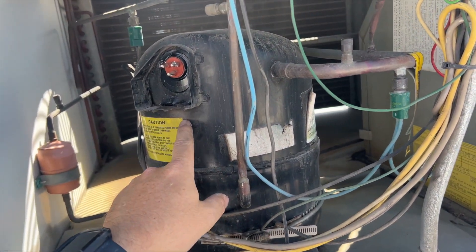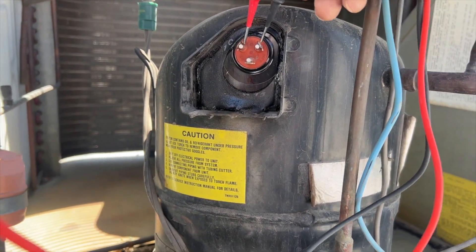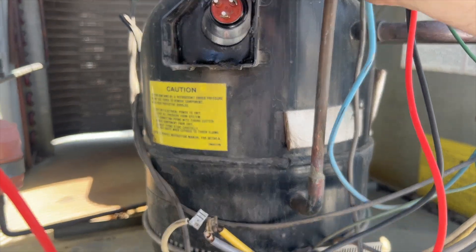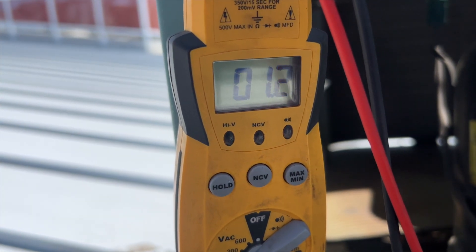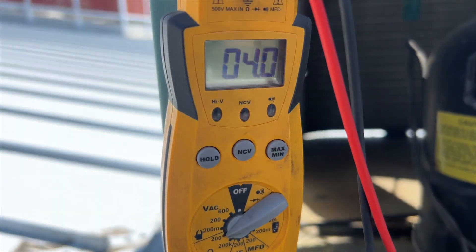We're going to go ahead and ohm out the compressor windings. Common to start: we're getting 3.3 ohms. Common to run: 1.1 ohms. So that means start to run should be 4.4 ohms. Checking start to run — okay, it's close. It's never going to be exact, but I'd say that's probably fine.